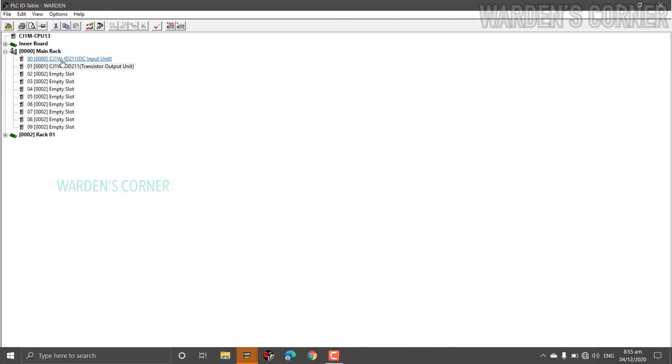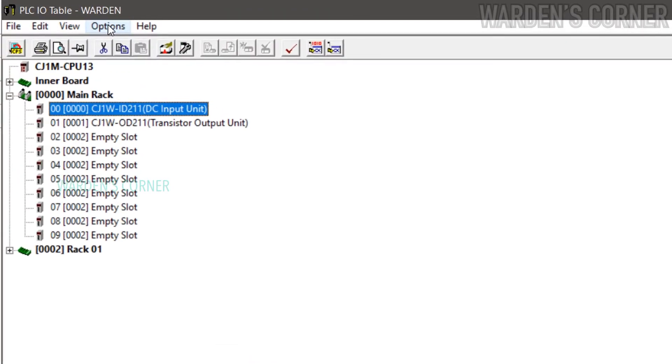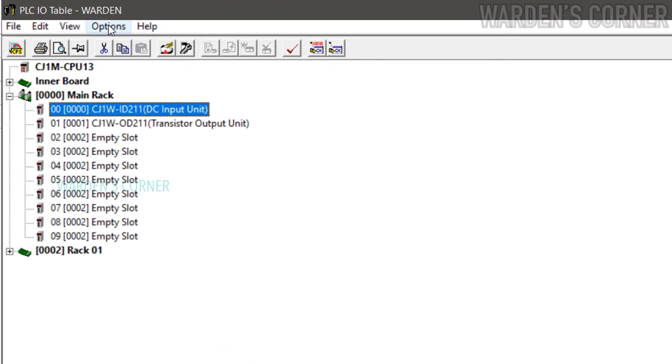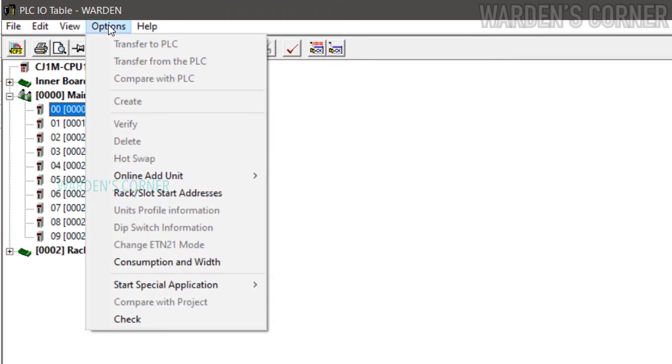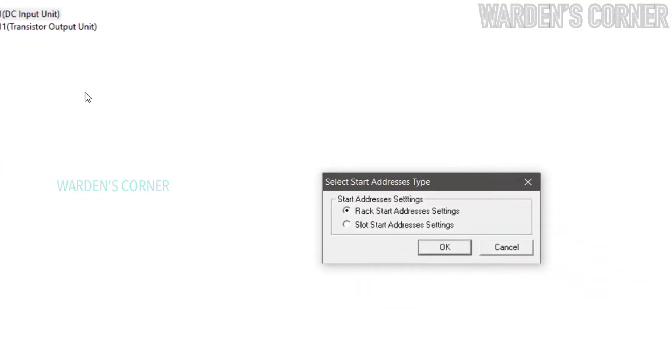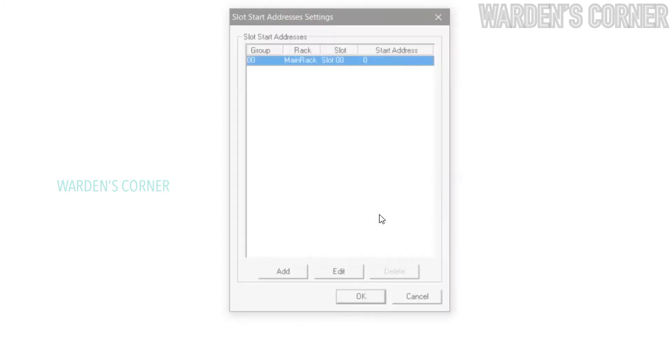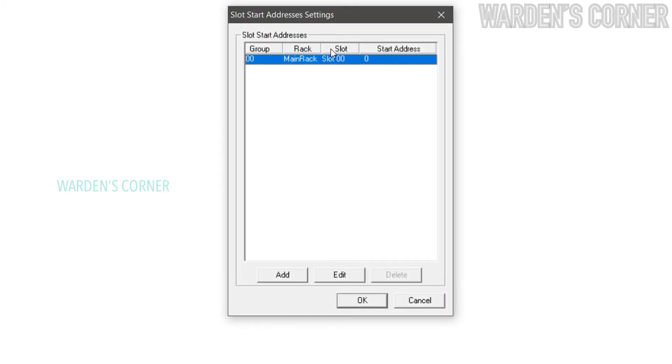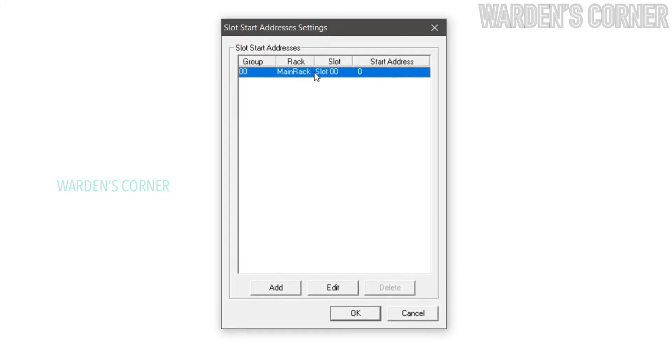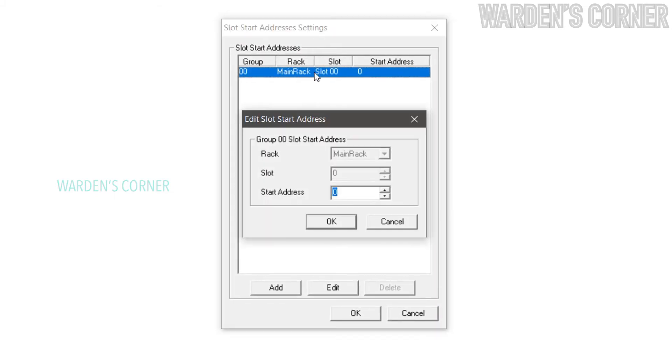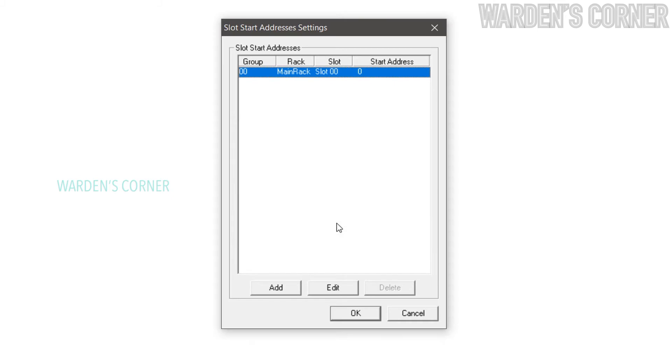Next, let's select the programming code designations for input and output cards. Go to Menu, click Options, select Rack/Slot Start Addresses. Select Slot Start Addresses Settings and OK. In the Start Addresses Settings tab, double-click Slot 00, choose your own addresses for input cards. You may start with 0 channel and click OK.